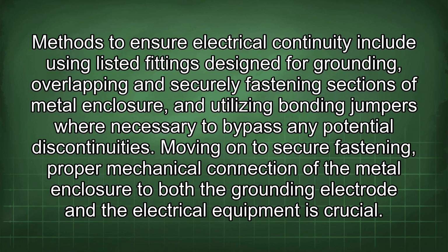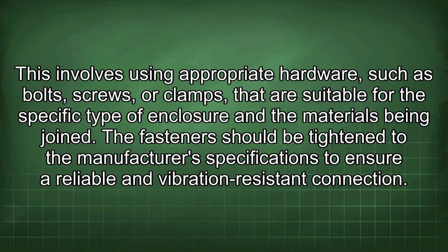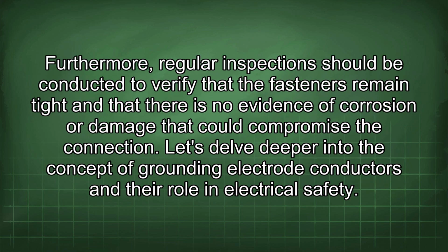Moving on to secure fastening, proper mechanical connection of the metal enclosure to both the grounding electrode and the electrical equipment is crucial. This involves using appropriate hardware, such as bolts, screws, or clamps, that are suitable for the specific type of enclosure and the materials being joined. The fastener should be tightened to the manufacturer's specifications to ensure a reliable and vibration-resistant connection. Furthermore, regular inspections should be conducted to verify that the fasteners remain tight and that there is no evidence of corrosion or damage that could compromise the connection.